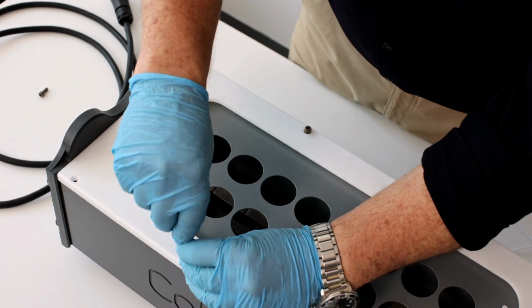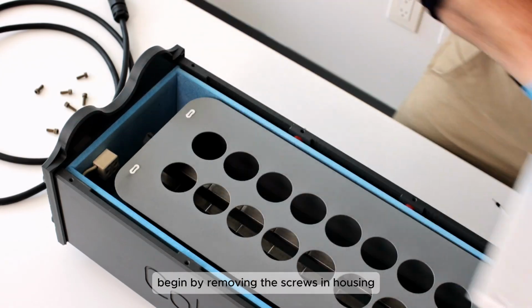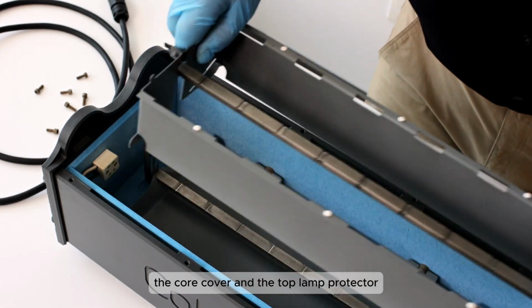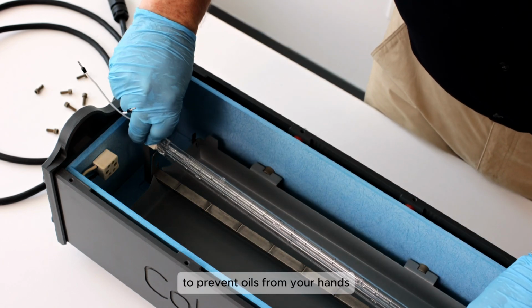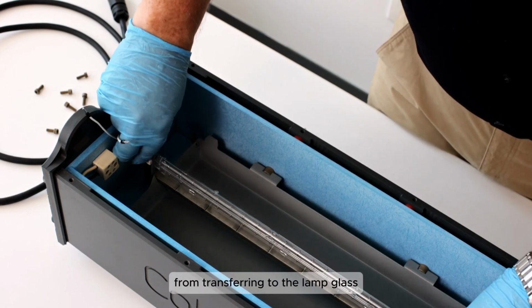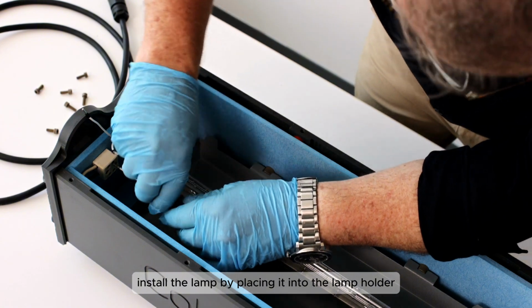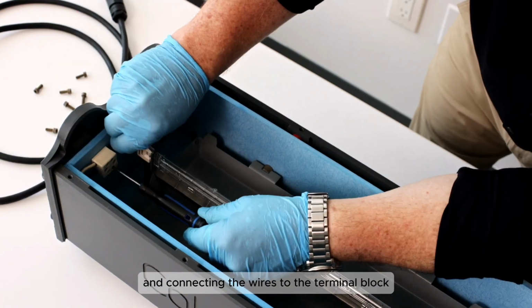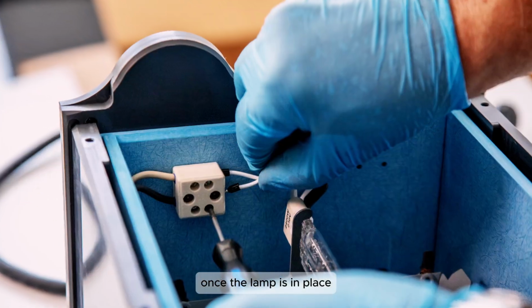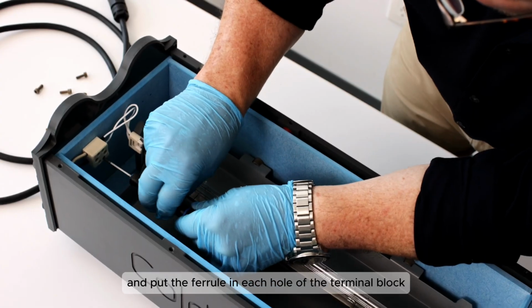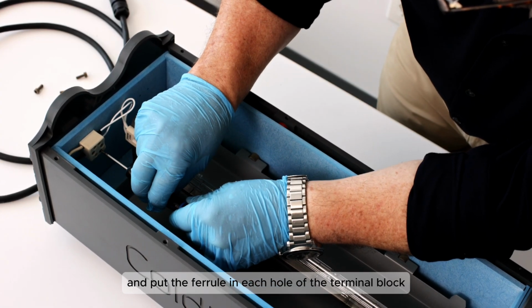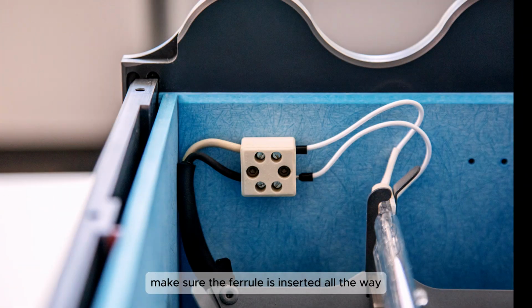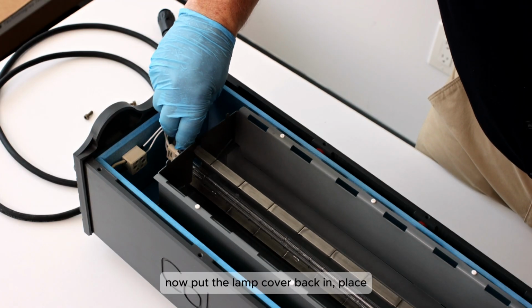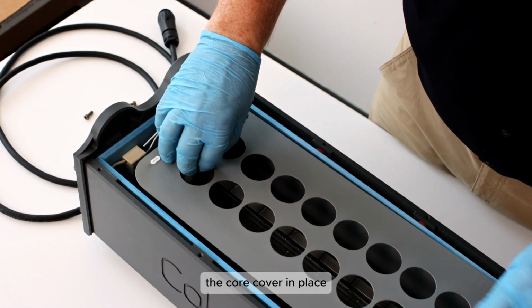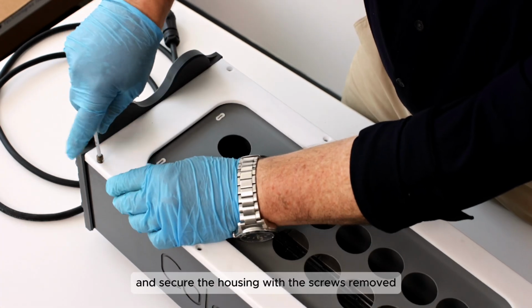Lamp installation. Begin by removing the screws and housing, the core cover and the top lamp protector from the heater. Wearing gloves to prevent oils from your hands from transferring to the lamp glass, install the lamp by placing it into the lamp holder and connecting the wires to the terminal block. Once the lamp is in place, take each wire and put the ferrule in each hole of the terminal block and tighten the screw. Make sure the ferrule is inserted all the way. Now put the lamp cover back in, place the core cover in place, and secure the housing with the screws removed at the beginning of this step.